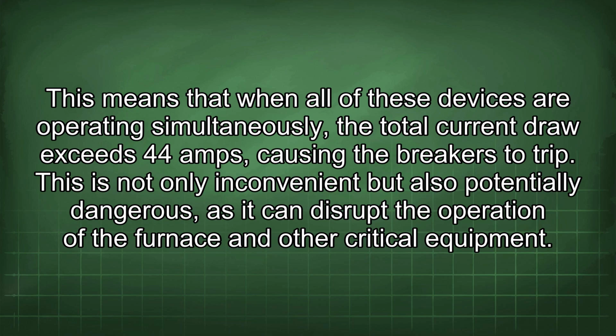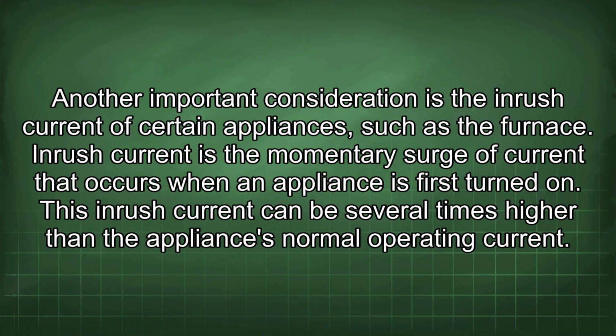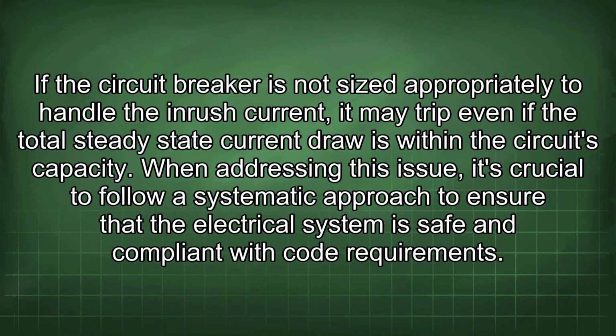Another important consideration is the inrush current of certain appliances, such as the furnace. Inrush current is the momentary surge of current that occurs when an appliance is first turned on. This inrush current can be several times higher than the appliance's normal operating current. If the circuit breaker is not sized appropriately to handle the inrush current, it may trip even if the total steady-state current draw is within the circuit's capacity.